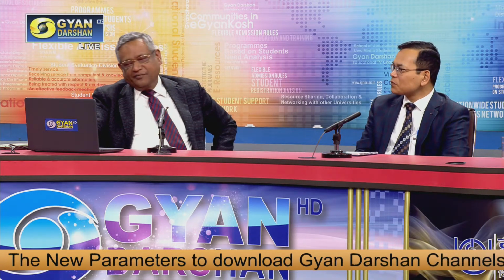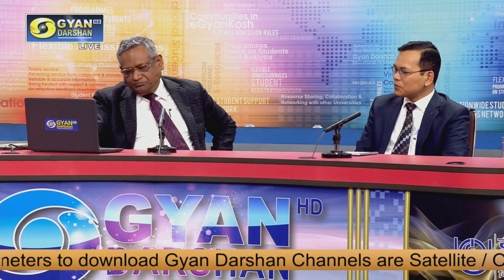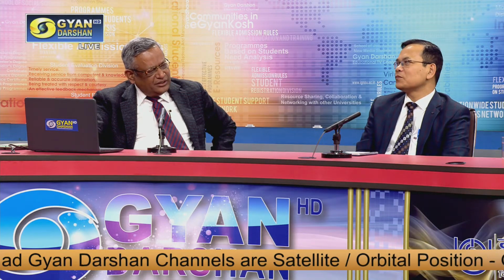Of course, you have to have a generator. We discussed that: first standby and second standby, and 100% backup, apart from the UPS. UPS load calculation: UPS has to be installed at least in the blood bank, the OT, the CT scan, the MRI, the cath lab, the LINAC. All these places you have to have a UPS. Technically, the vendor gives it as a part of the equipment. But you can have a centralized battery room and a centralized UPS where the cable can connect to the respective equipment located on various floors of the building.